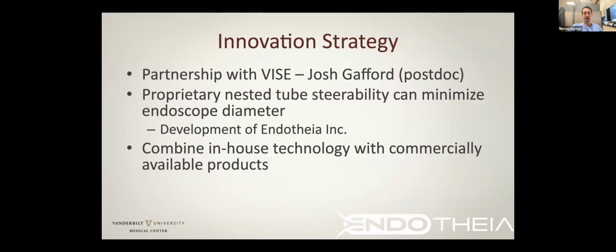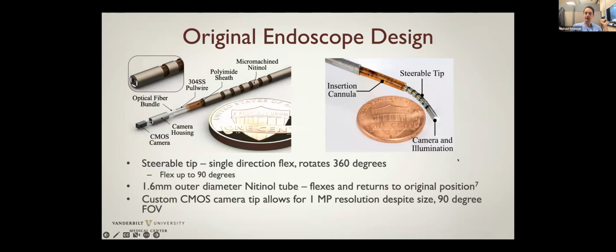This technology branched out into a private company, Endotheia, that's based in Midtown, which applied for and obtained an SBIR grant. The idea behind it is combining that in-house proprietary technology with commercially available micro camera technology. This is our original endoscope. You can see a photo of it on the right. It's very small. It's 1.6 millimeters outer diameter and provides 1 megapixel resolution, but was only able to steer one direction and flex only up to 90 degrees.